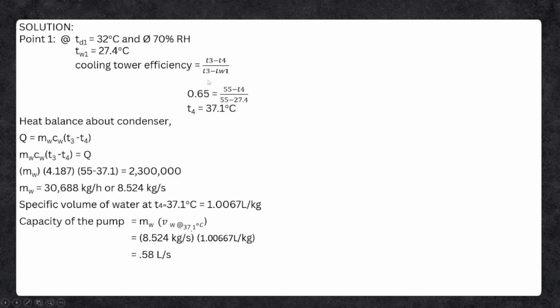So, the formula for cooling tower efficiency is T3 minus T4 over T3 minus TW1. Substituting the values: 0.65 equals 55 minus T4 over 55 minus 27.4. We get the value of 37.1 degrees Celsius for temperature 4.